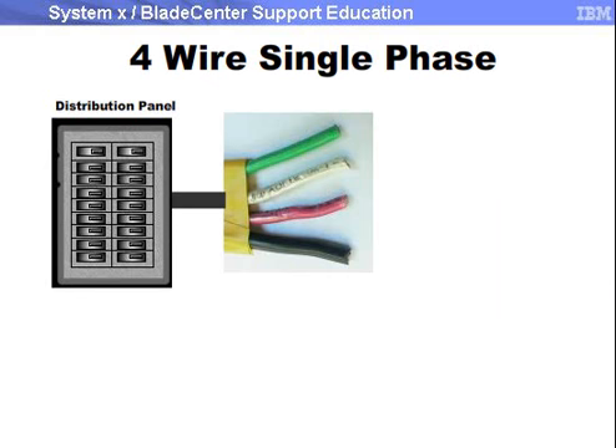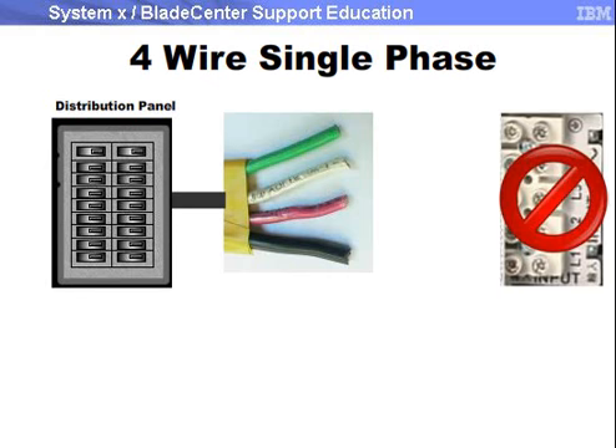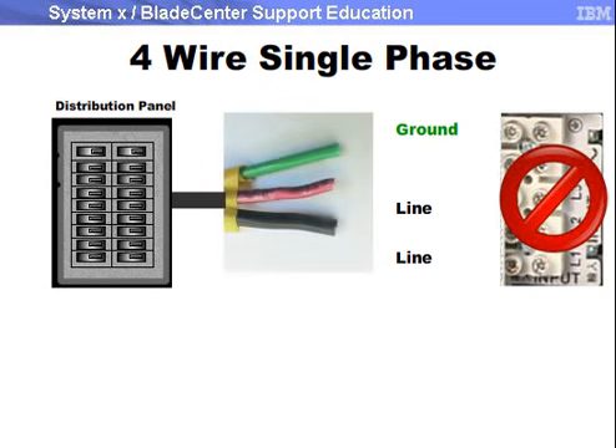4-wire single-phase wiring is not supported by the 7500XHV or the 10000XHV. 4-wire single-phase wiring consists of 2 supply wires, a neutral wire, and a ground wire. A 4-wire single-phase run will need to be rewired as a 3-wire single-phase connection by removing the neutral connection run from the distribution panel to properly connect the UPS.